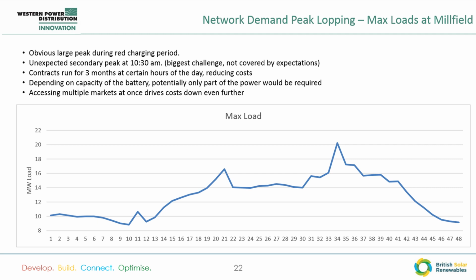And all peaks over 16 megawatts, if we took 16 as our arbitrary limit that we wanted to use the battery to reduce, for instance, all occur within the winter months, meaning you wouldn't need a network support contract year round. You'd only need it for the 3 winter months. If not all of the battery power was needed, then this would reduce the cost of the service even further. Although quite how that would work, and whether the battery would be able to use the rest of its capacity to import, would have to be negotiated with the DNO.